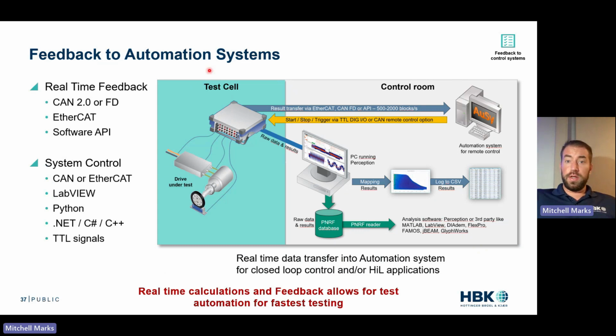And we offer feedback to automation systems. Because we do all our calculations in real time, we can feed answers back to the automation system at 2 kilohertz. So as soon as you have your measurement, you can move to the next point, measure the next point, measure the next point, with a really nice handshake where we can feed back over EtherCAT, CAN, API at up to 2 kilohertz. And we can receive start, stop, trigger, change range, change reading over CAN, EtherCAT, LabVIEW, Python, or .NET, C#. We have an API. So real-time calculations and feedback allow for test automation so you can test at the fastest rate, so you can save more time and more money.